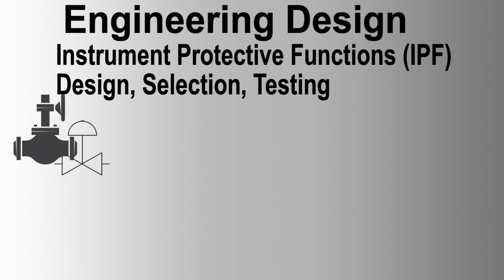If a revealed failure robust component fails, the other should continue to operate in crippled mode. In this mode, a time limit of up to 72 hours, actual time limit depends on the application and should be stated in the requisition, should be defined to allow for sufficient repair time of the faulty component. Without corrective action, and after this period, the outputs concerned should de-energize. The time outstanding should be transmitted to the DCS for operator information.